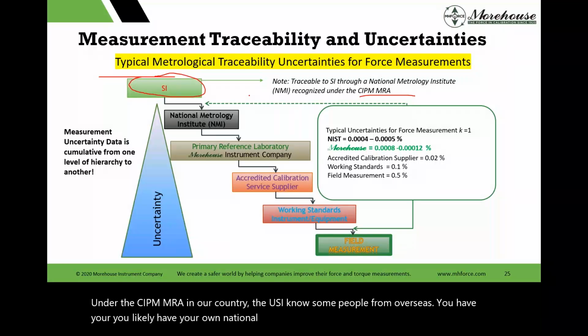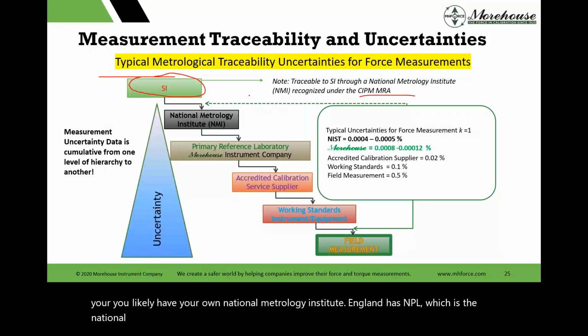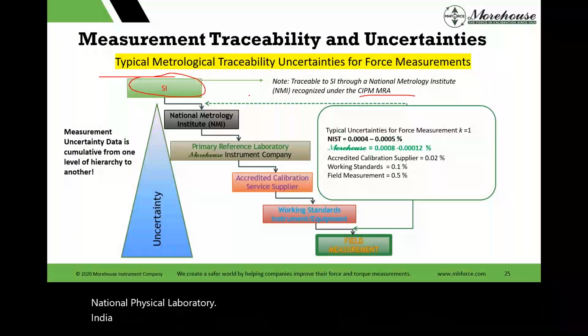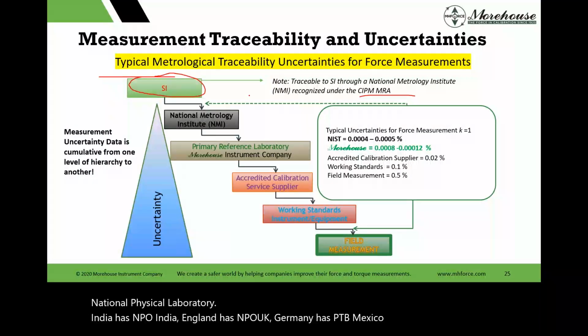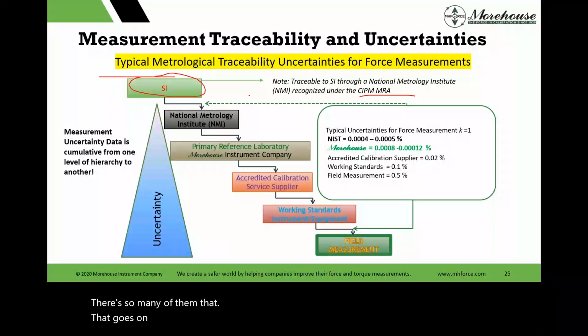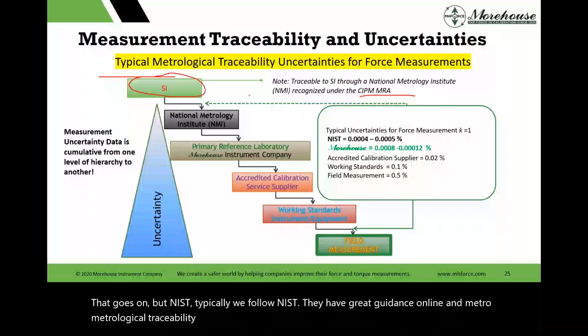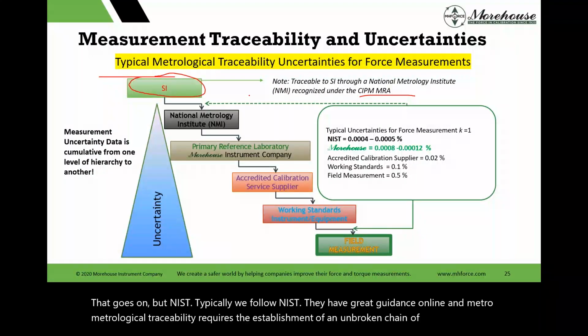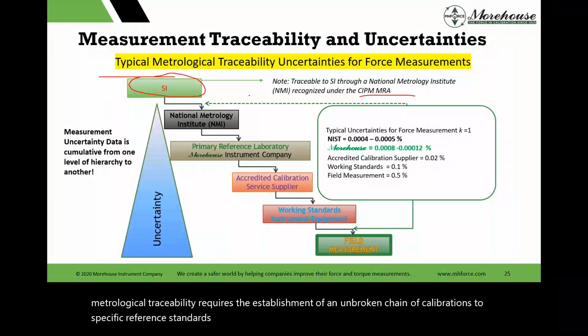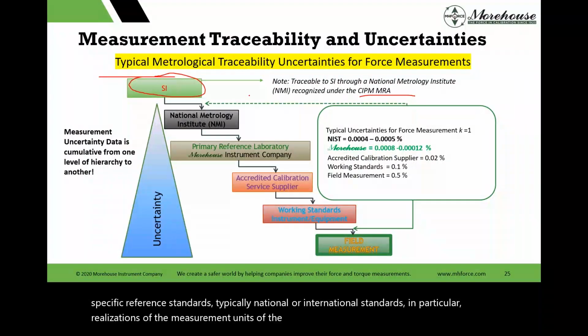In our country, the U.S., I know some people from overseas, you likely have your own National Metrology Institute. England has NPL, which is the National Physical Laboratory. India has NPL India, Germany has PTB, Mexico has CENAM, and so on. There's so many of them. But NIST, typically we follow NIST. They have great guidance online, and metrological traceability requires the establishment of an unbroken chain of calibrations to specific reference standards, typically national or international standards, in particular realizations of the measurement units of the International System of Units.